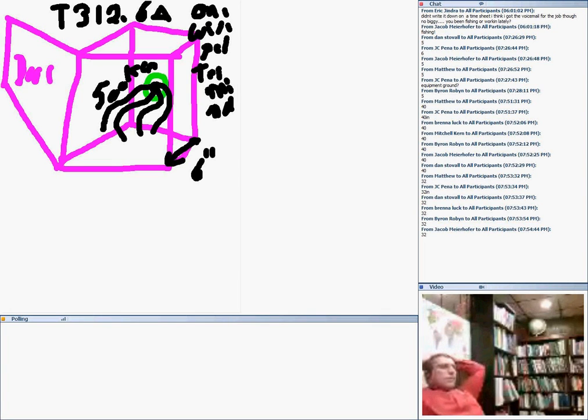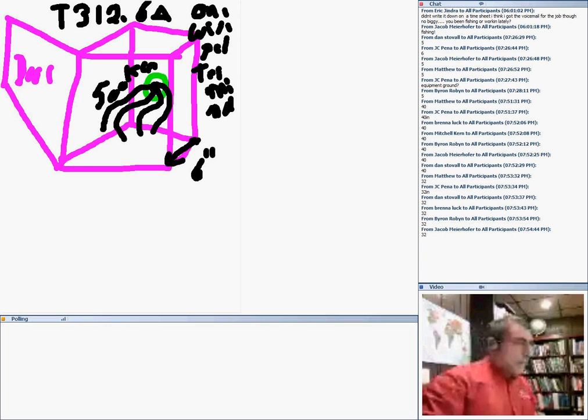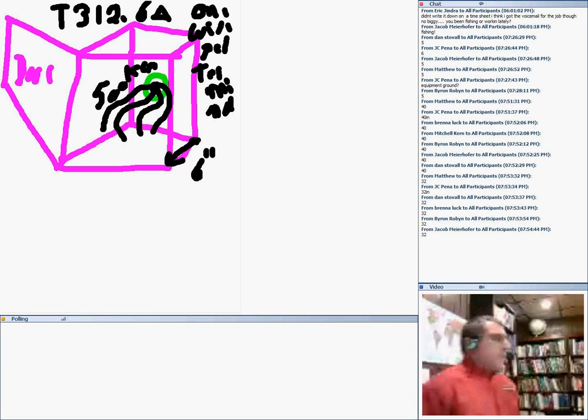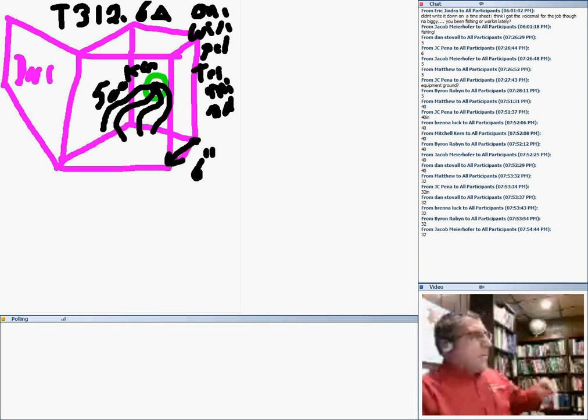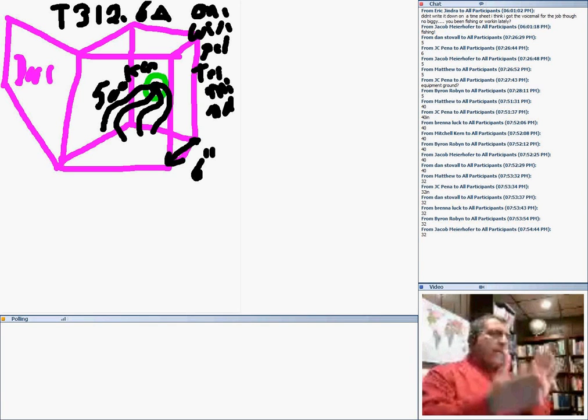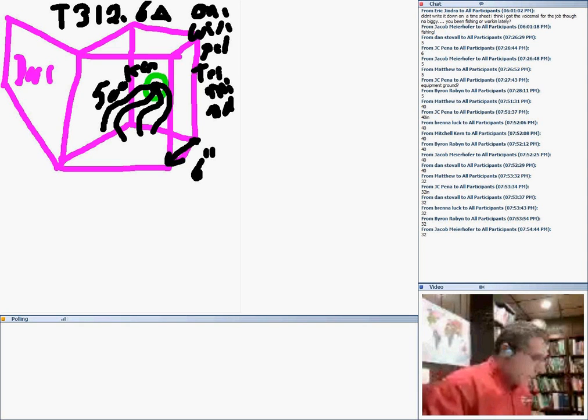And that's on a journeyman exam. Repeat. And guys, so I can see that you guys are moving. Any question one more time? That's a special case, which is the depth of a box. It comes from the back to the front, where there is a door. It doesn't have to be back to front, guys. Joe, it could be side to side, as long as the conduit enters from one side and the opposite side is a door or a removable cover. A door, removable cover, anything you can remove. That is, you can pull the conductor easily if you can remove it, if you can get your hands in there, and you can get your hands in if that side is removable. It's an exception that the state of Minnesota likes to put in your journeyman exam.